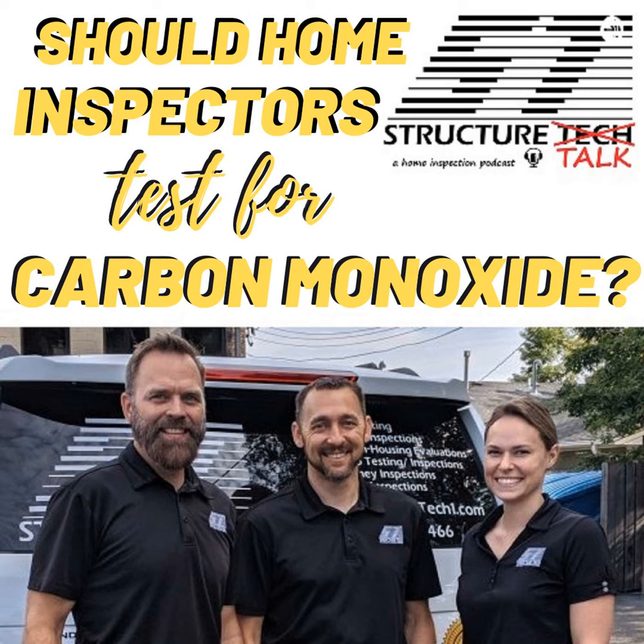What it depends on. If we're talking about a furnace, you just stick it in the middle of the flue. But if it's a boiler, and most boilers are going to be natural draft, you're going to want to stick it all over that flue. You want to put it on the far left side, take a reading there, move over to the center, move over to the right side. You got to move your probe around. And we did some training at somebody's facility once, and they had a perfect demonstration of that, where you put it on the left side of the flue and the CO was very low. You move it over to the right side and it just skyrocketed. So on a furnace, in the center, but if it's for a boiler, you want to move it around inside there.